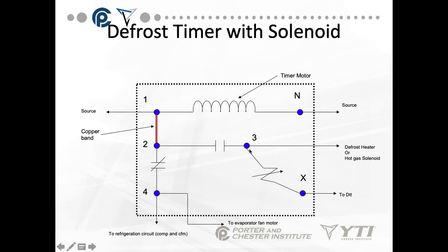Between pins 2 and 3 there's a normally open contact — meaning we're not in defrost. Between pin 2 and 4 we have a normally closed contact, meaning when we're not in defrost, this is a closed circuit between 2 and 4. Pin 3 goes to the defrost heater or hot gas solenoid. Pin 4 goes to the refrigeration circuit: compressor, condenser fan motor, and evaporator fan motor.